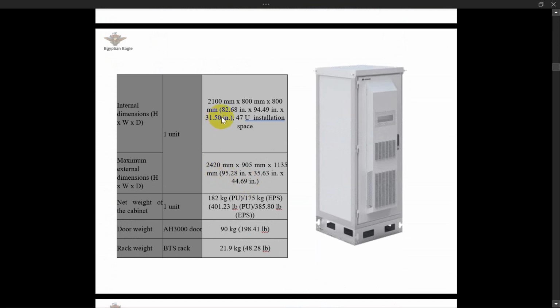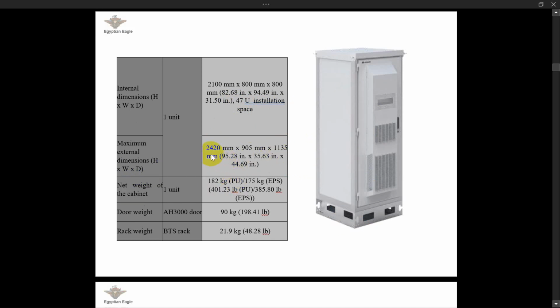The dimension of the BTS is 2 meters 10 centimeters high, 80 centimeters width and 80 centimeters depth inside. It can hold 47U inside, so we can fix the BTS 3900L with space from below and above for cable routing. The outside dimensions are 2 meters 24 centimeters, 90 centimeters, and 113.5 centimeters.